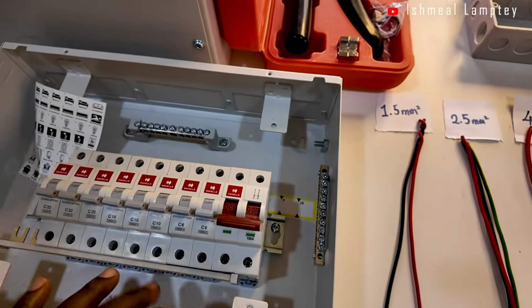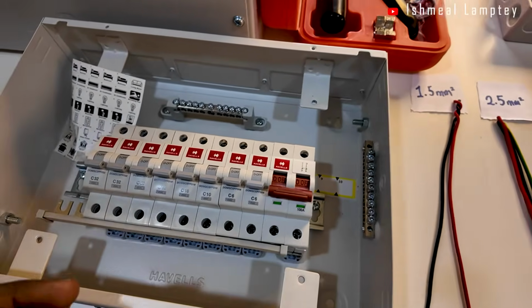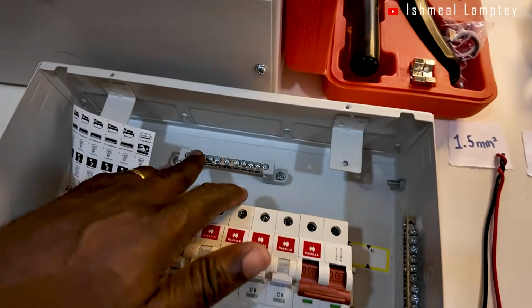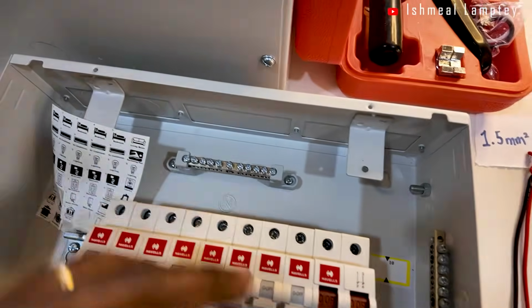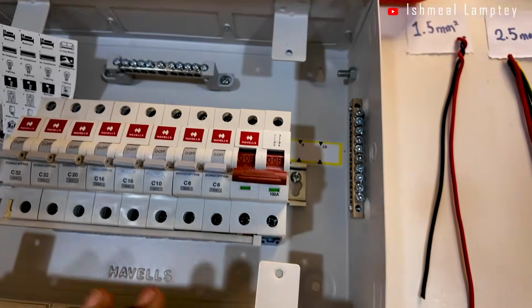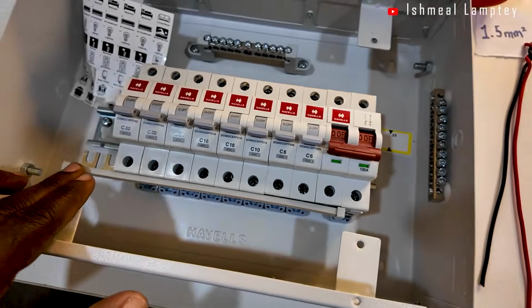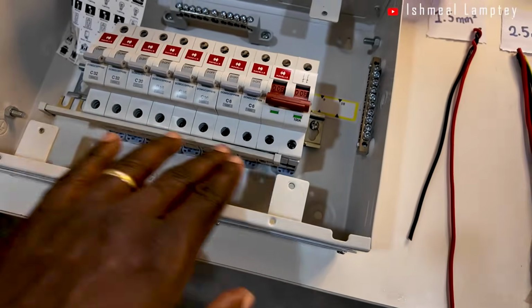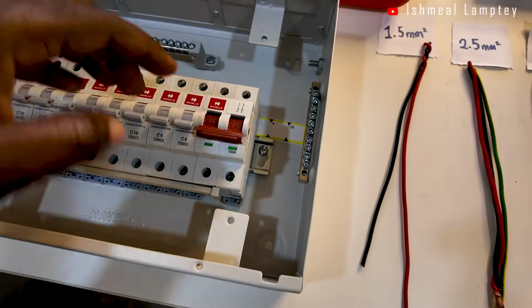For this particular panel or distribution board, if you look closely, there are different things in there. There's a bus bar - this is the neutral bus bar, it's written there. This is the earth bus bar, also written here. And then the live is distributed using this bus bar too, distributing the power, so you have your power lines.